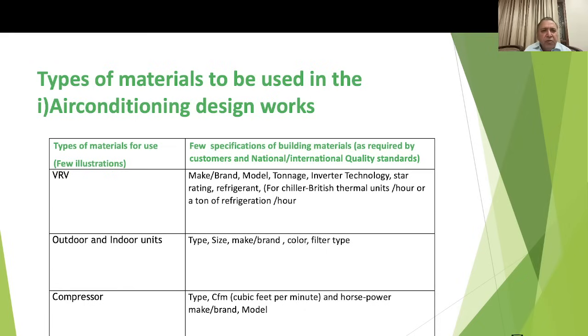For air conditioning materials, the main key items are VRV outdoor units and compressors. For VRV, designers need to specify the make, brand, model, tonnage, inverter technology, star rating, and type of refrigerant. For outdoor and indoor units, specify the type, size, make, brand, color, and filter type. For the compressor, specify the type, make, brand, and CFM rating or horsepower.